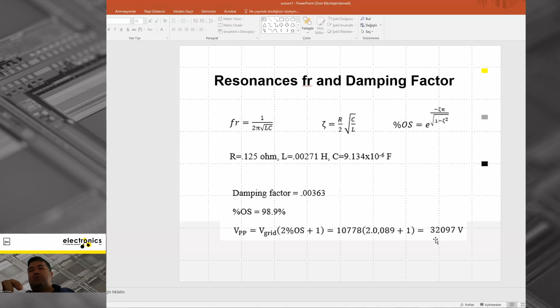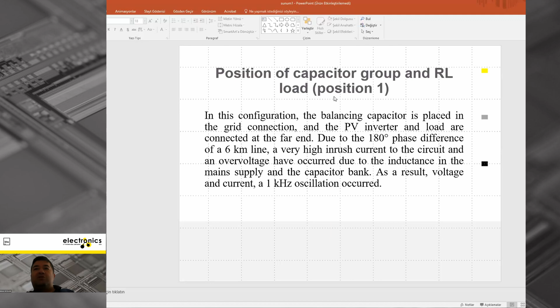And according to the first scenario, we calculated about 30,000 volt peak voltage, and we change the position of the capacitor group and RL load, position 1 and position 2. In position 1, the balancing capacitor is placed at the grid connection, and the PV inverter and load are connected at the far end due to the 180 degree phase difference of the 6 kilometer line. A very high inrush current to the circuit and overvoltage occurred due to the inductance of the main supply and the capacitor bank. As a result, voltage and current 1 kilohertz oscillation occurred.